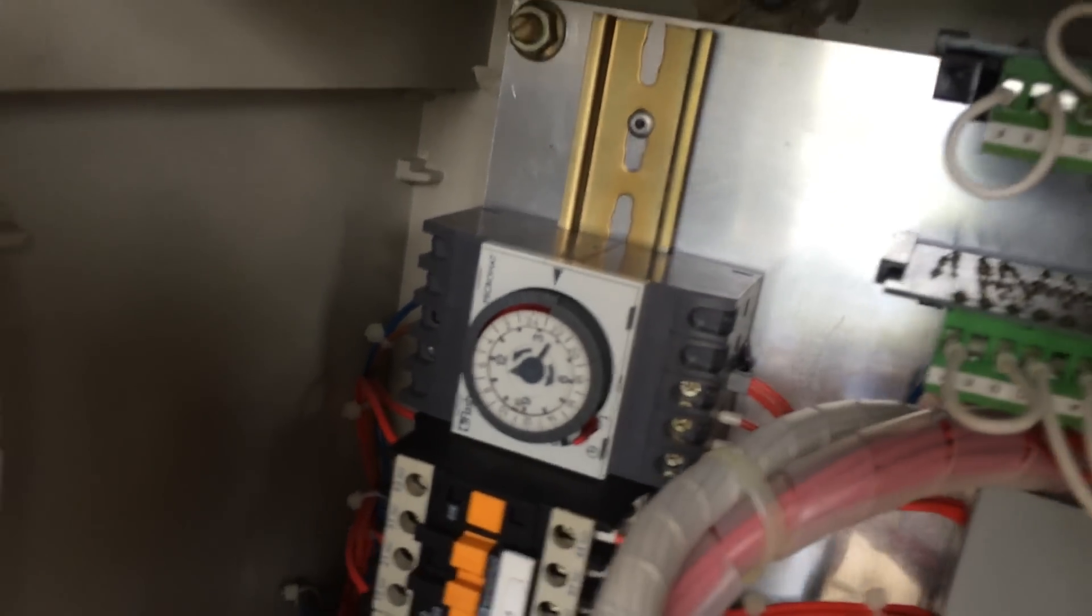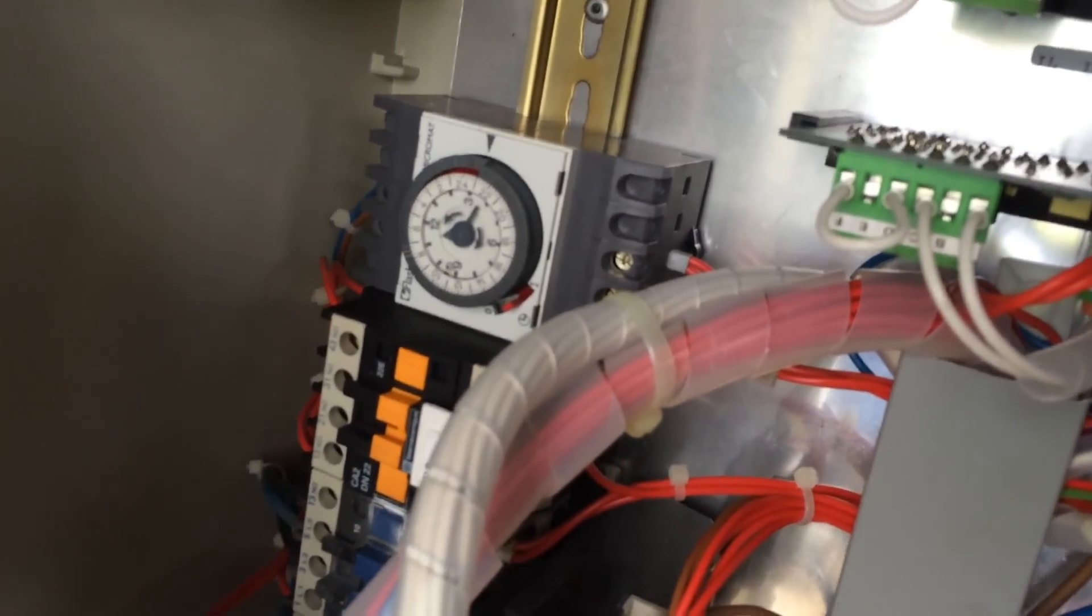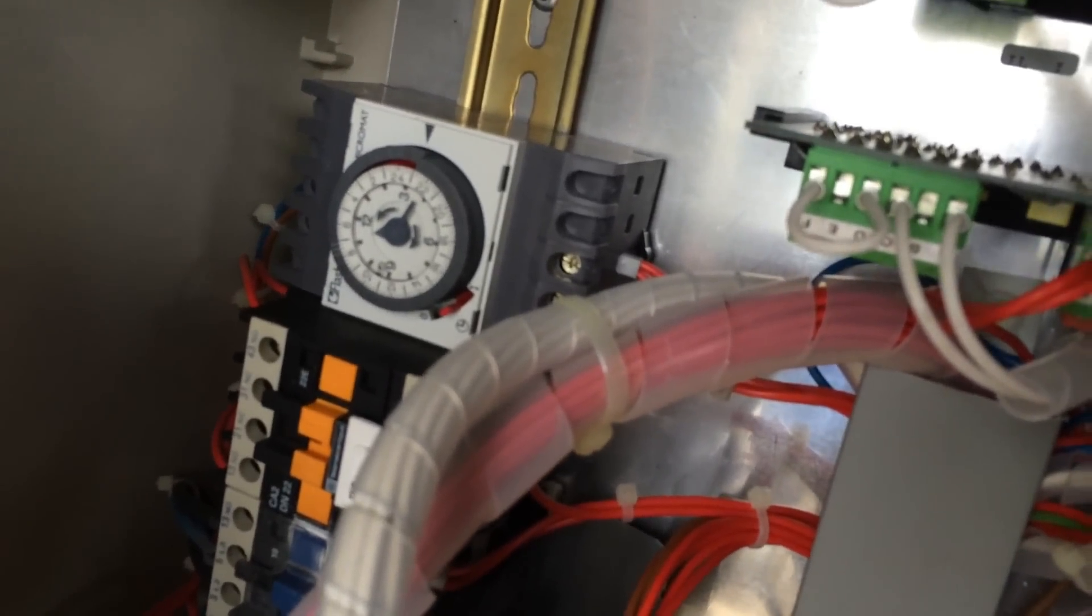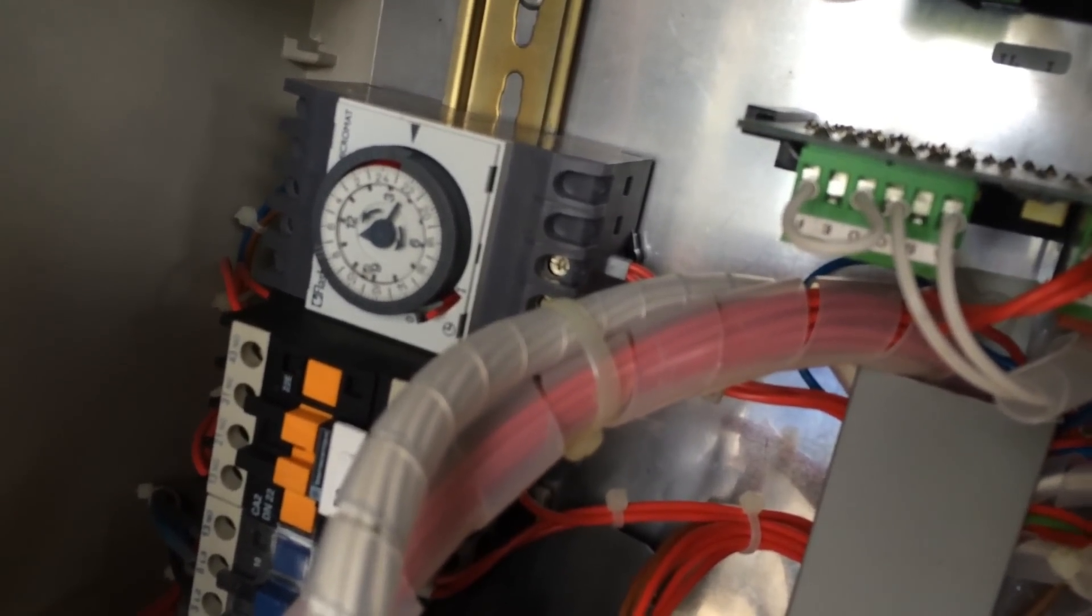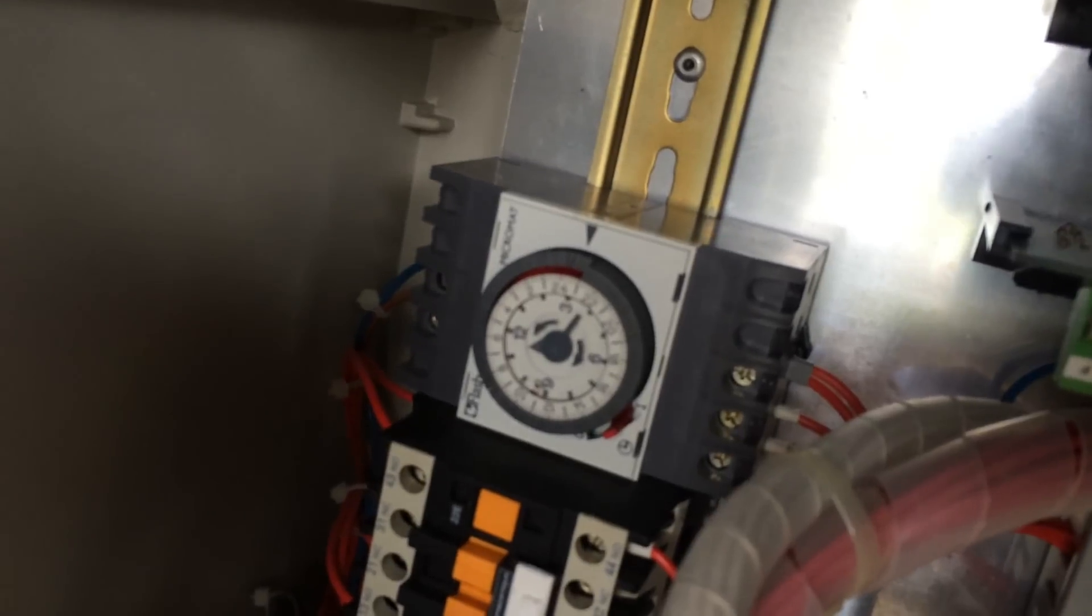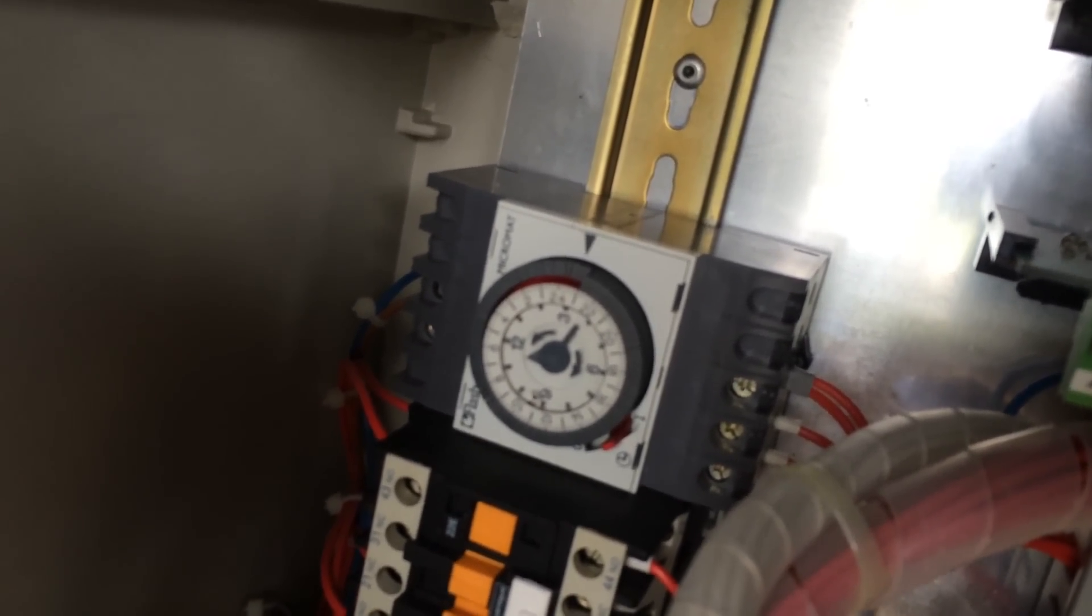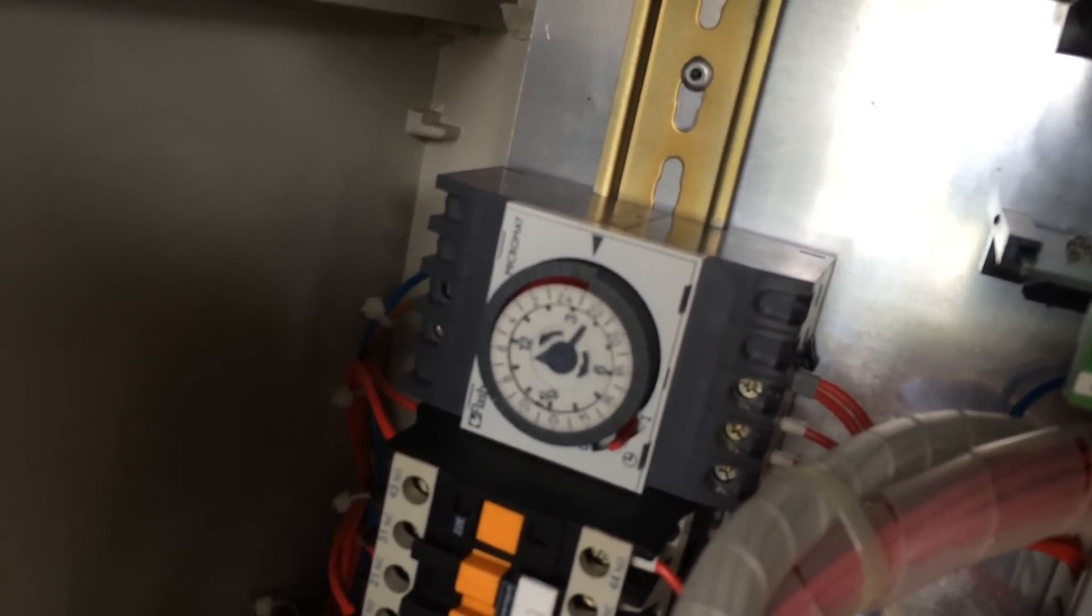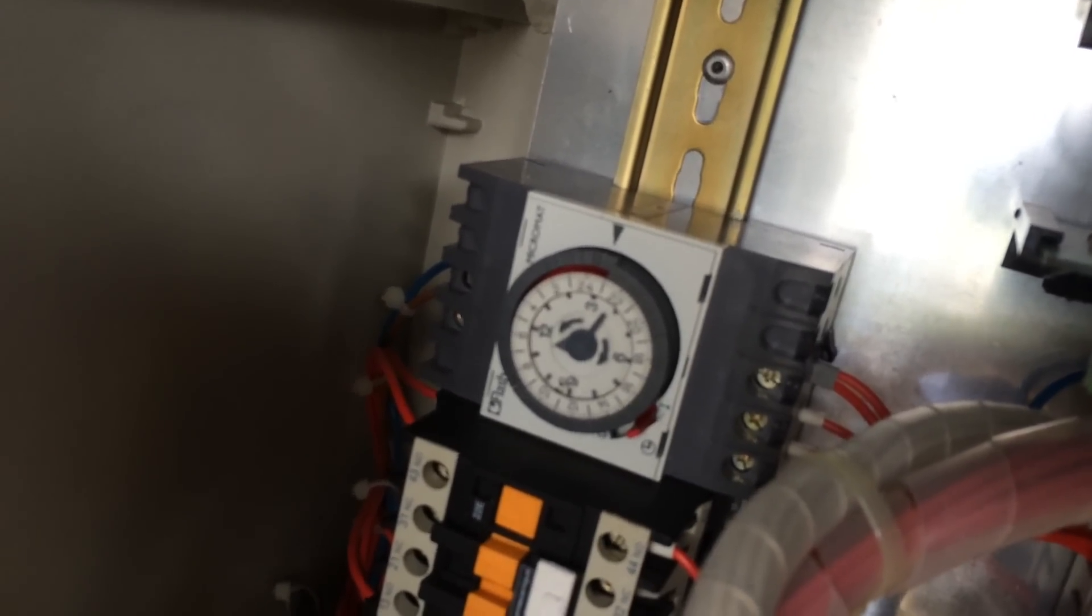When the clock is off, it has a low ice function that will keep about a quarter of an inch of ice over the whole coil, and that's all it will do. So if it had been operating on that to get the milk cold, it would have only had half an hour run time, and there's no way it would have made that much ice in that time.